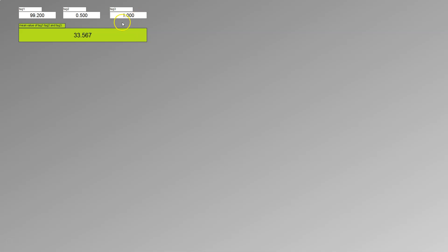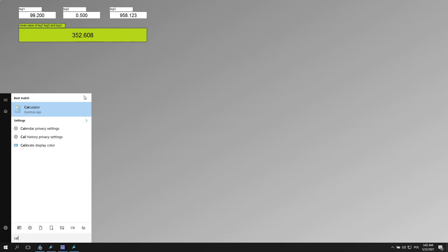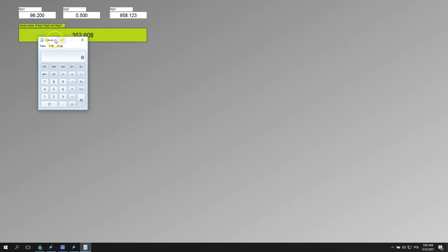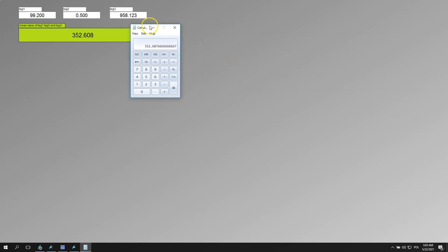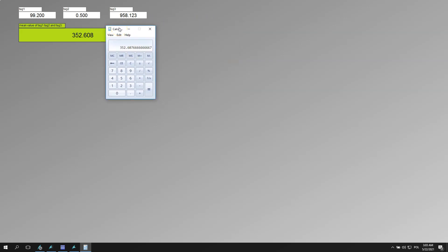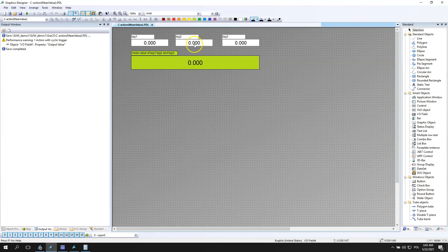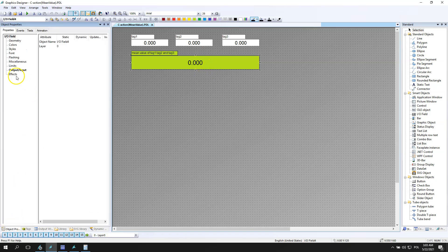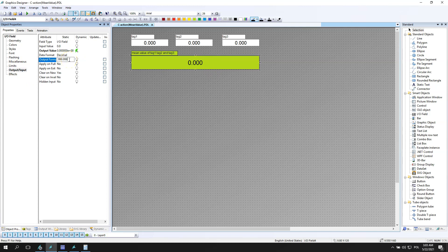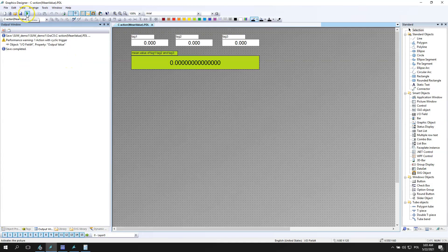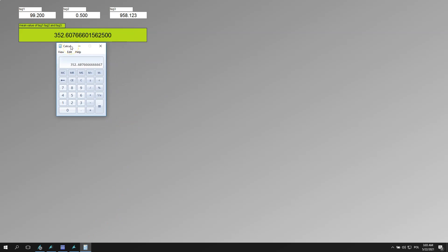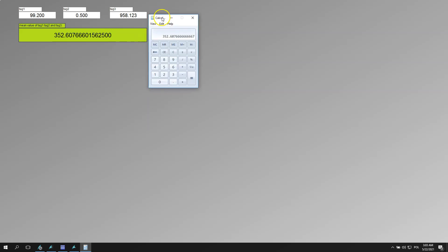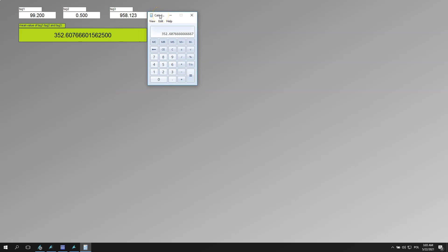Now you can provide some functions, some floating point values, and this system provides you the exact mean value of these three elements. Of course the resolution of these mathematical things depends on the floating points and the floating point inside WinCC. Let's check the calculator and the mean value of our system. I provide all the numbers and we need to divide by three, so we have almost the same but we have different resolution of our output. Now I can try to make more, but let's check if we can have the same value. It looks we don't have. The resolution inside WinCC is different than the resolution inside the calculator. Probably we should use the double floating point to make the same. If you want to try this, try inside your system.